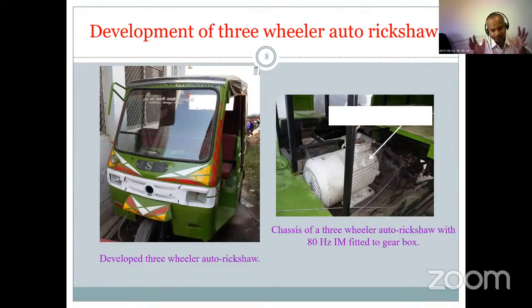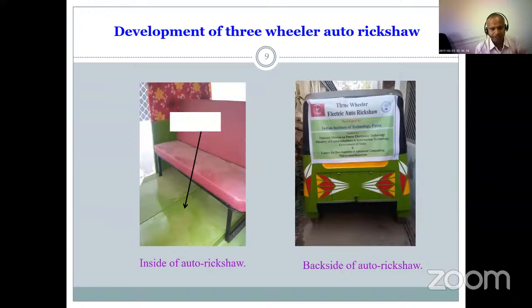It operates at 80 hertz, because in India the roads are not similar and are very rough and tough, so you require a wide speed range. That's why 80 hertz, 110 volt, and 5 HP. This motor has an efficiency of more than 92%, and it is patented and granted.